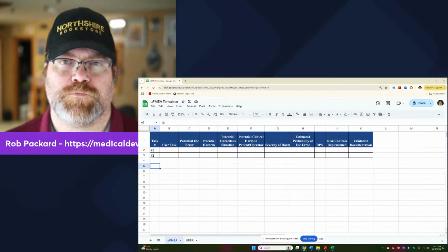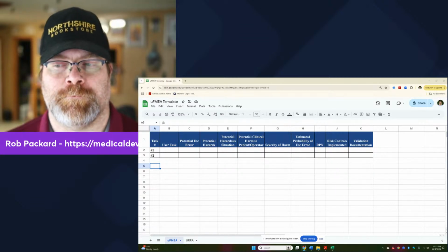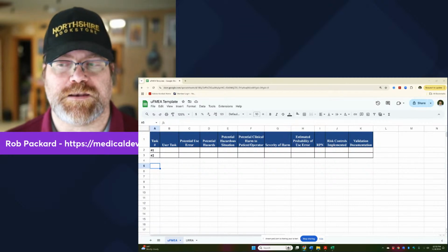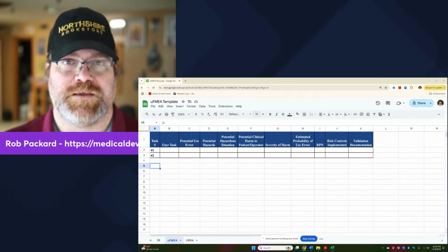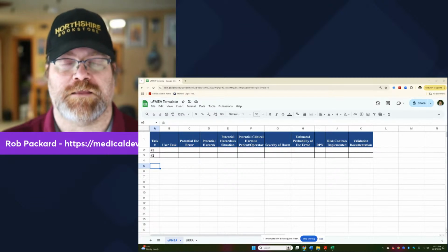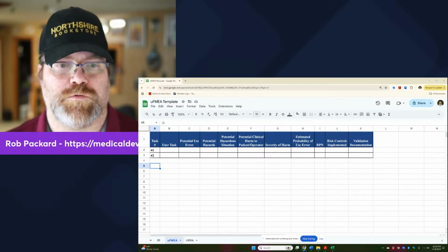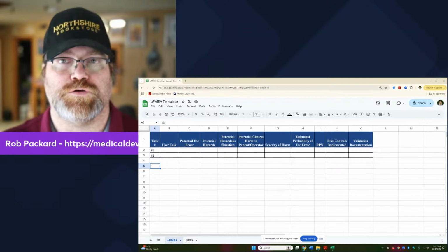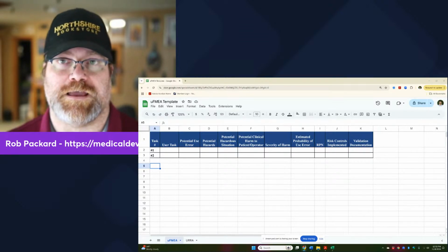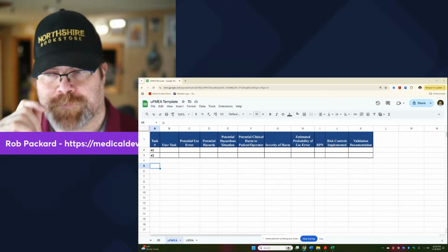But usually where people stop, they like to do the minimum. They will stop with, here's what it says step by step how to use the device. So that's what I've written in the instructions for use, and that's what our use FMEA is based on. The 10 steps to perform the use of our product. Let's say it's taking a temperature with an infrared thermometer, for example.